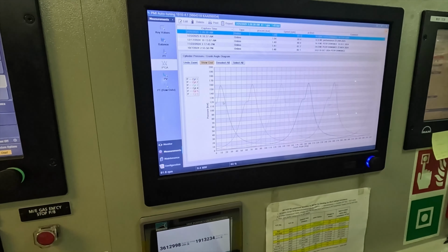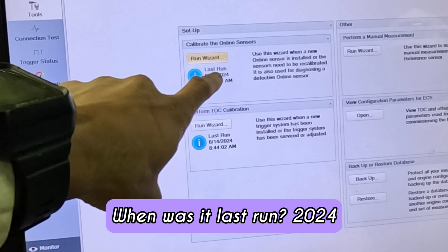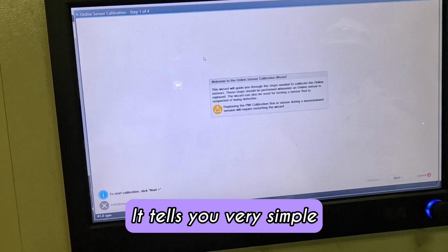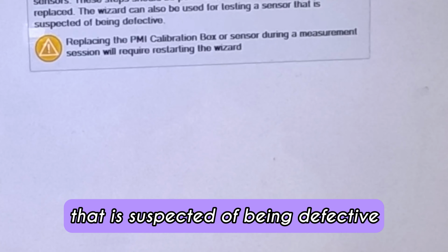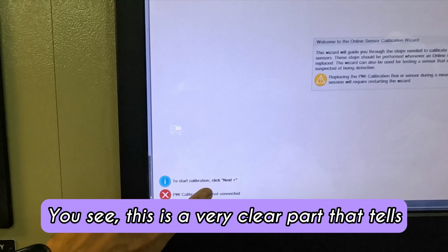In the PMI app, can you go to the maintenance? See, when was it last run? 2024. So click on run the wizard. It tells you very simply. Can you read through? This wizard will guide you through the steps needed to calibrate the online sensors. These steps should be performed whenever an online sensor is replaced. The wizard can also be used for testing a sensor that is suspected of being defective. Just go on next. This is a very clear part that tells you.